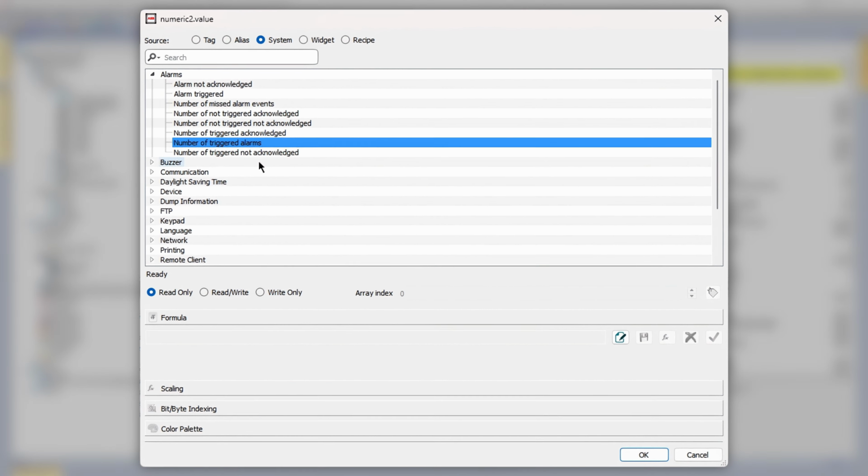Link the visibility property to the alarm trigger tag, and add the ability to navigate to the alarms page when the operator taps on the widget. Add a hotspot button, make it wider, add a load page action, and place it behind the label widget. Let's see whether it works in the simulation. When I trigger a couple of sensor alarms, the widget appears and the combined description text with vertical separation lines scrolls horizontally.